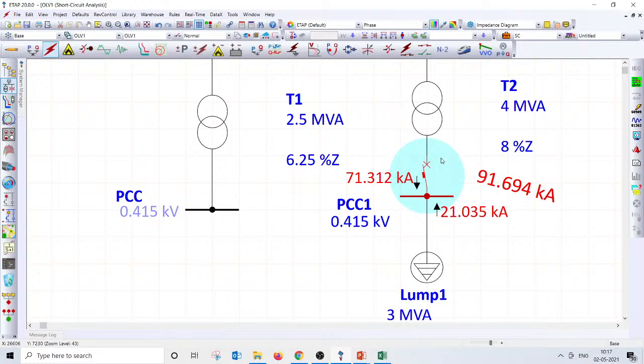At least, even if you put a 75 kiloamp breaker for an incomer, that's sufficient, because the short circuit contribution from the transformer is only 71 kiloamps. But you will have multiple outgoing feeders, and in the worst case 91 kiloamps can flow if there is a fault immediately after any LV circuit breaker, right? So that's the real reason why we predominantly limit the transformer rating to maybe 2.5 MVA.